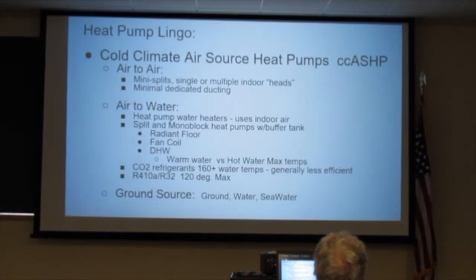There's several different types, which we can get into more if we have time. But because I'm only making warm water, I have a radiant floor in my little house, so that's perfect—100 degree water, it's happy. I boosted it up with my regular domestic hot water heater up to 115, and that seems to work fine. There's also fan coils, I can show you one.